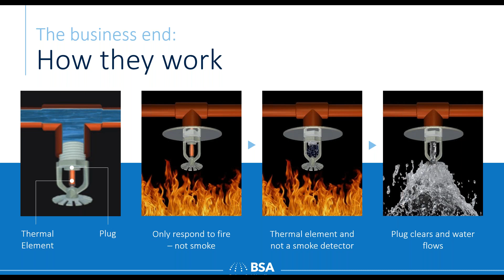Just to give you an idea of what a sprinkler head looks like in operation, here are some simple videos. Sadly, the video is not playing, but I'll explain these. In the top left on your screen, you can see just a standard head operating. And then in the bottom half of the picture, you'll see two different heads operating. These are what we would refer to as storage heads. The difference between the two is the larger umbrella pattern. And in the picture on the bottom right, that's what we call an ESFR head. Again, a very large umbrella pattern, and you're also seeing a spike.